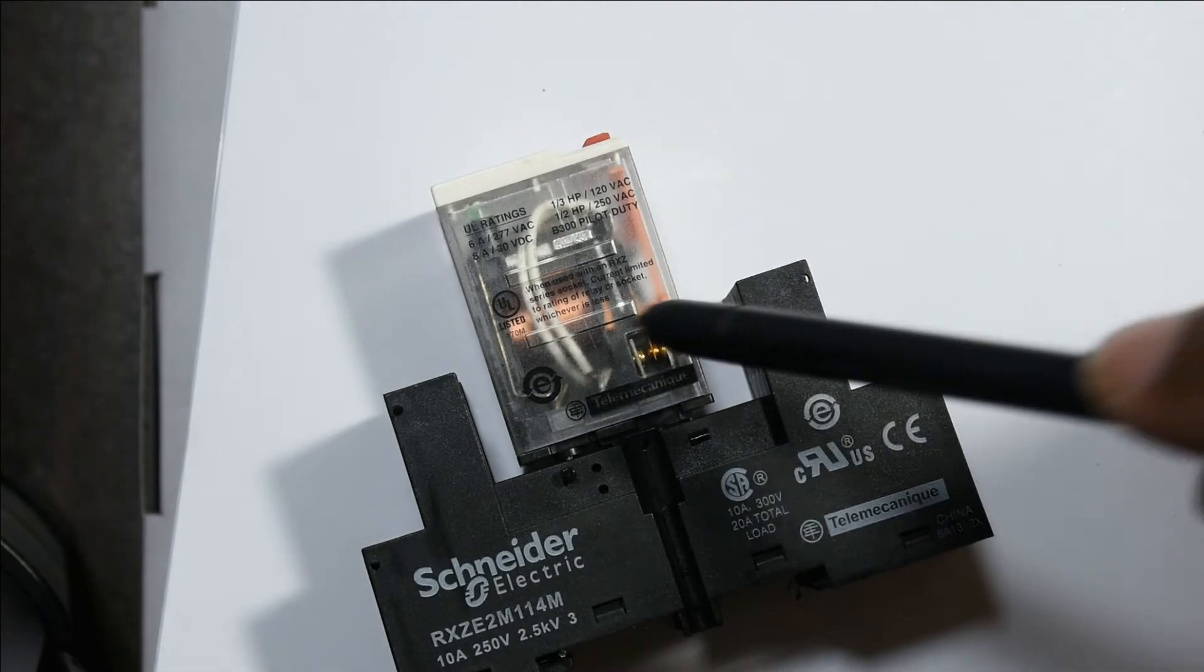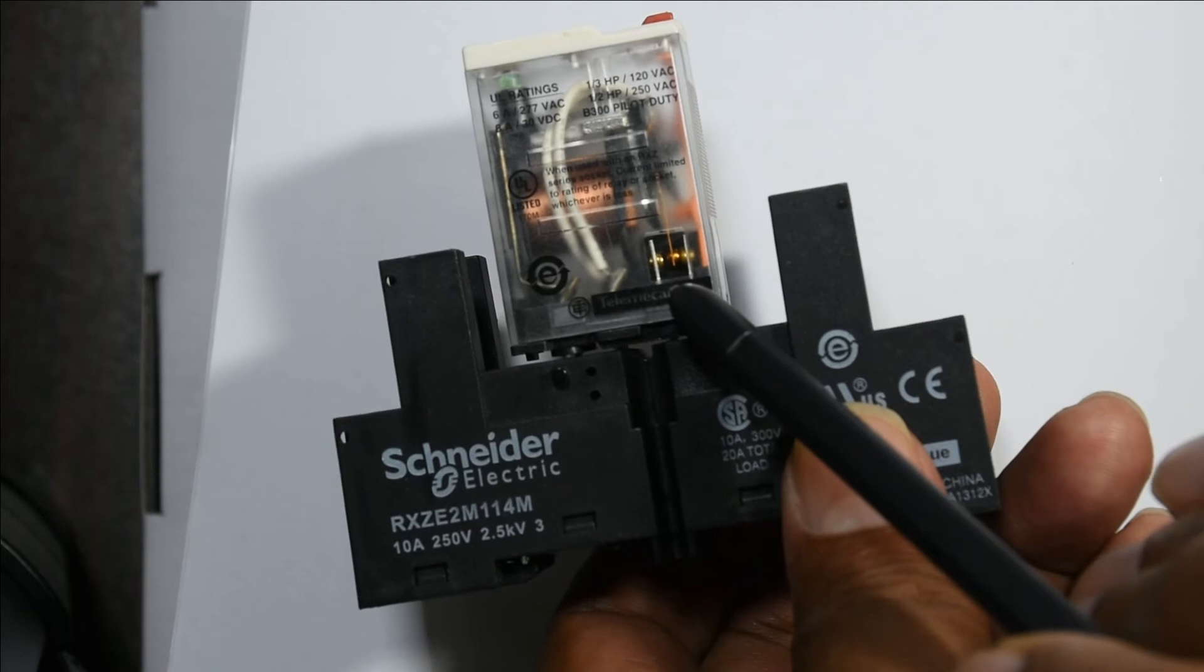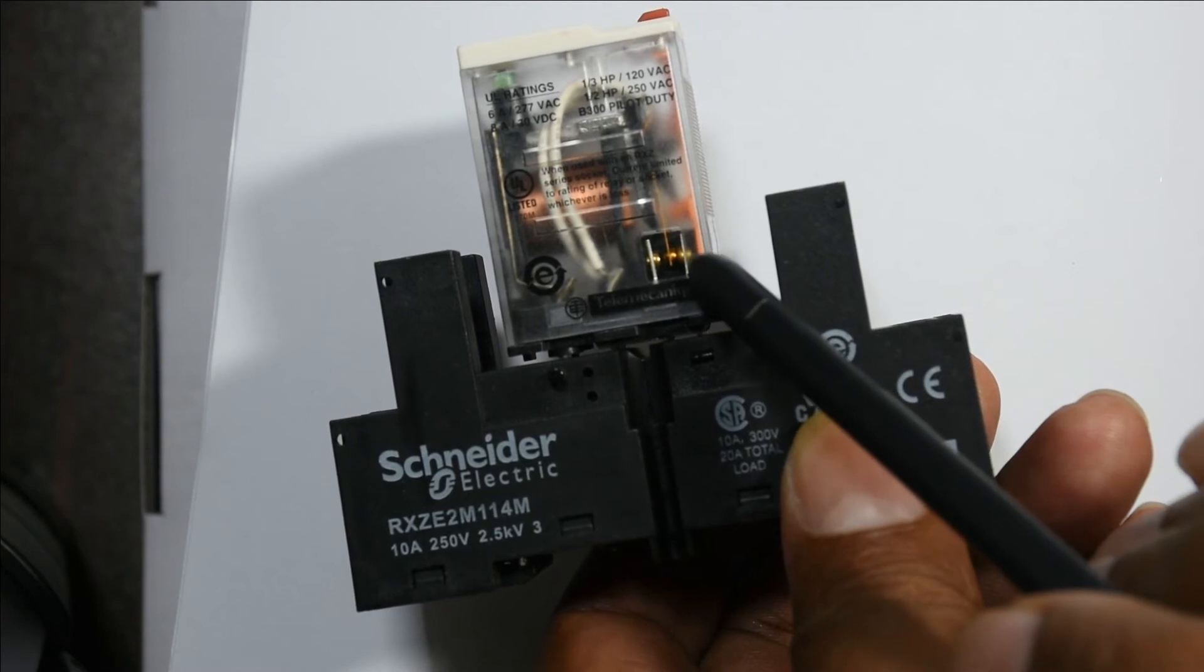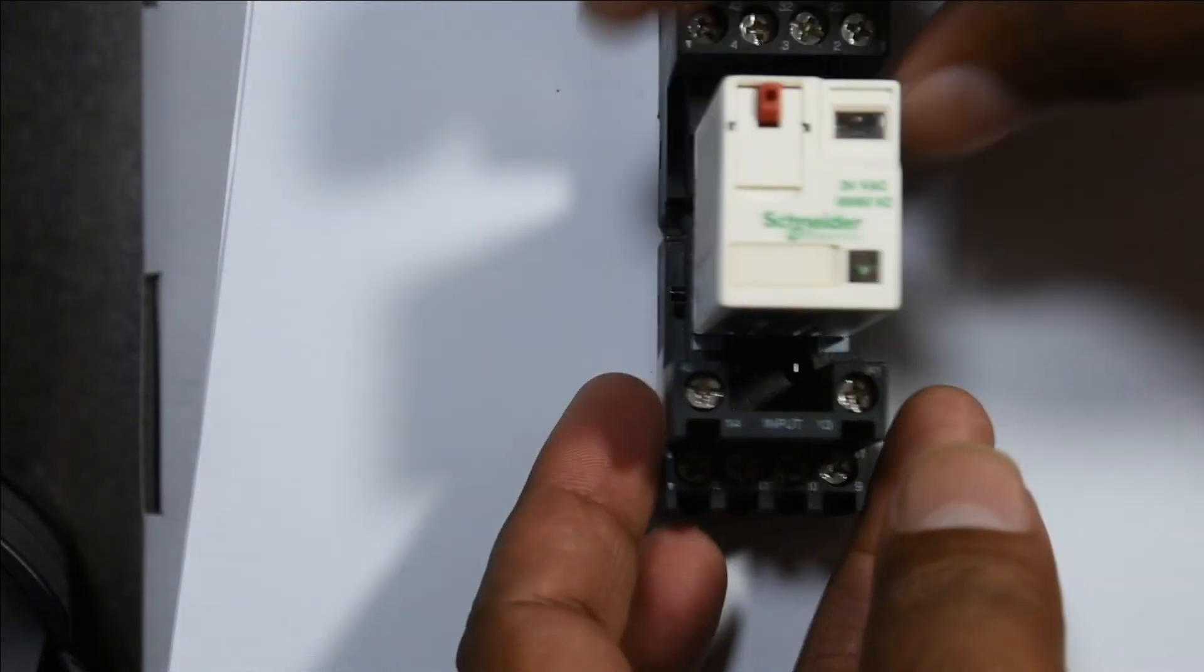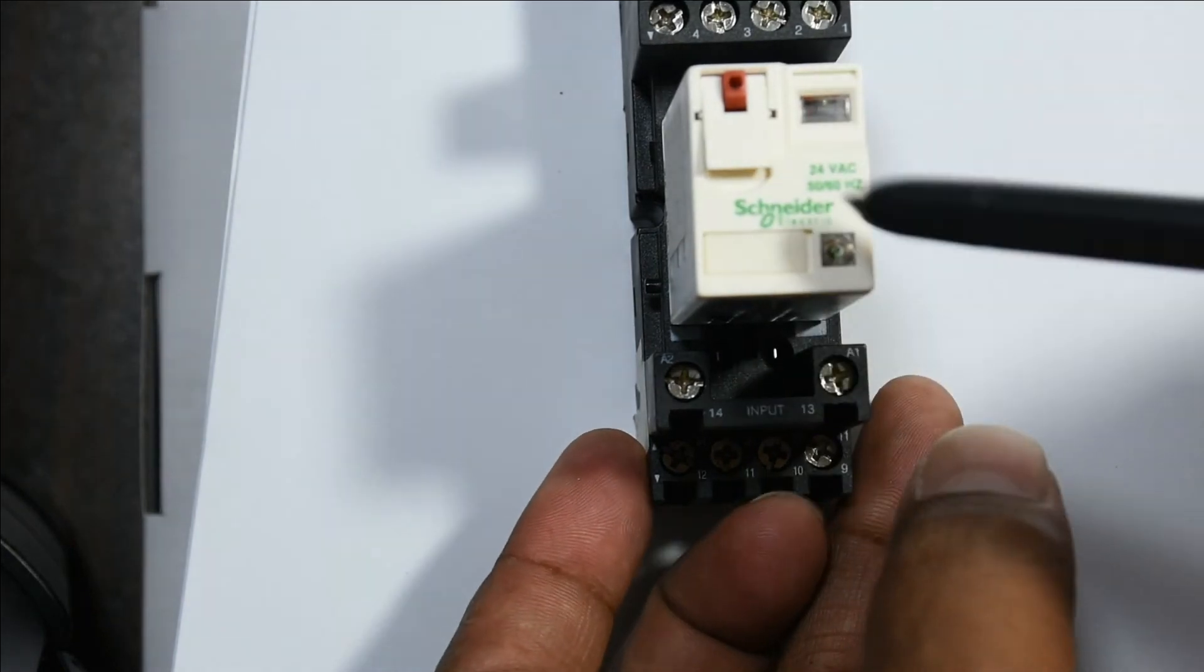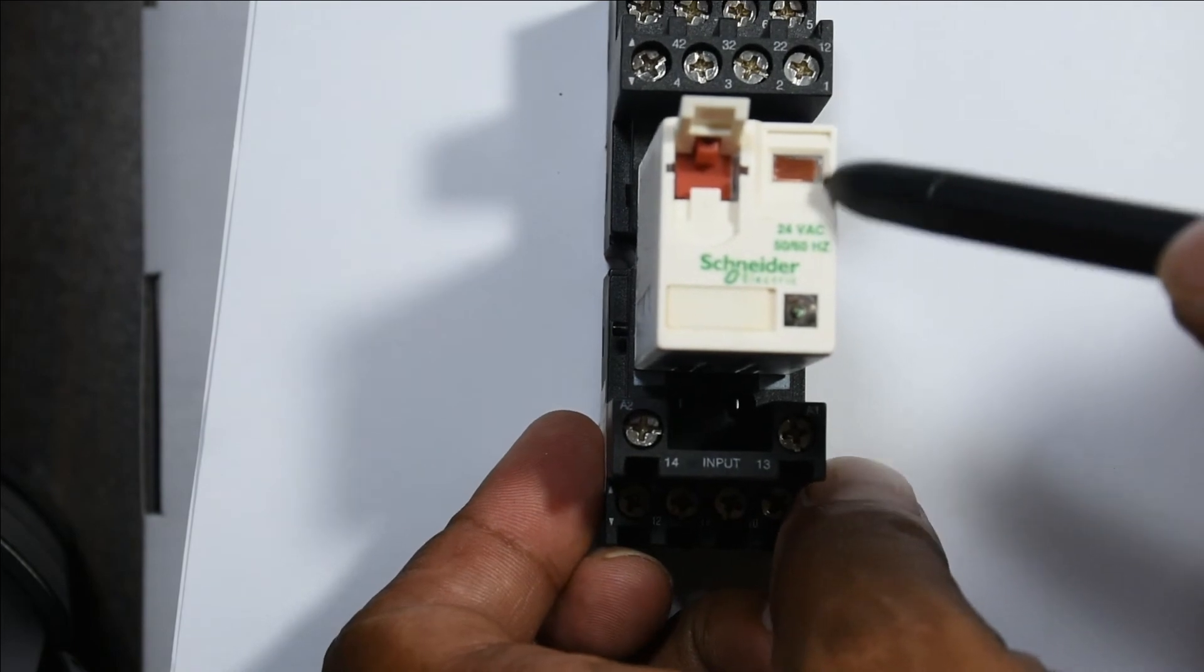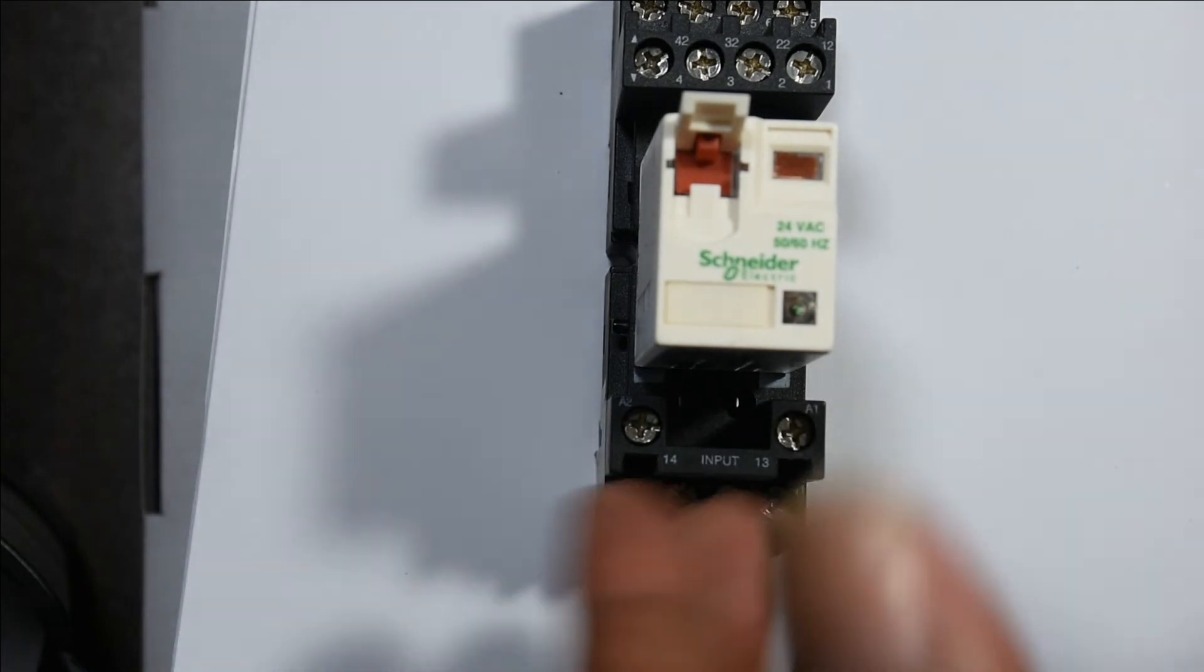Inside is the coil. Here are the contacts: normally open, the common in the middle, and the normally closed contact. We have the advantage that we can bypass this relay. When you open it here, this will close the relay, indicated by the orange tab. There's also an indicator LED which shows when the coil is active.